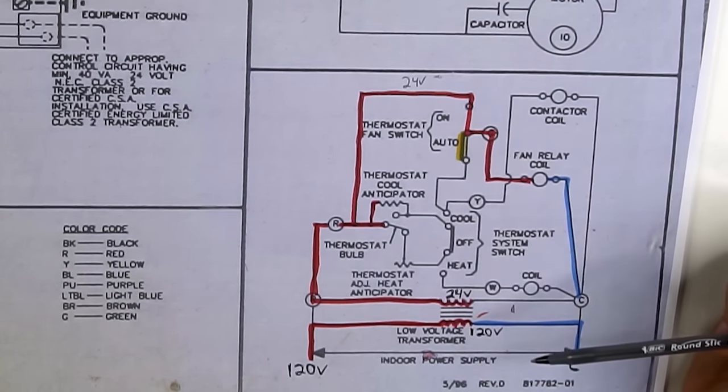This one is actually vertical. Just like the other ones, we have our schematic diagram in ladder form on this side. Even though it says ladder diagram, notice how the potential relay is all in one spot, and the dual run capacitor is also in one spot — not spread out. So this isn't exactly a true ladder diagram; they're just trying to make it easier to read. We have our ladder diagram on this side and the connection diagram on the other side. Unlike the other diagrams, this one actually has a bunch of notes and information at the bottom — always a good idea to read through all notes and special instructions before trying to diagnose.